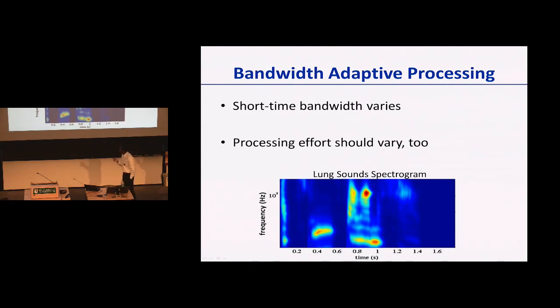So the idea of bandwidth adaptive processing is this: lung sounds coming from a patient's chest do not have a constant bandwidth. As you can see from this spectrogram, the bandwidth varies quite a bit over time. Now, a conventional sensor is designed so that it is always able to handle the maximum worst case expected bandwidth of the incoming signal. That's a pretty wasteful design strategy, because it's only very rarely that the signal actually takes up that entire maximum bandwidth.